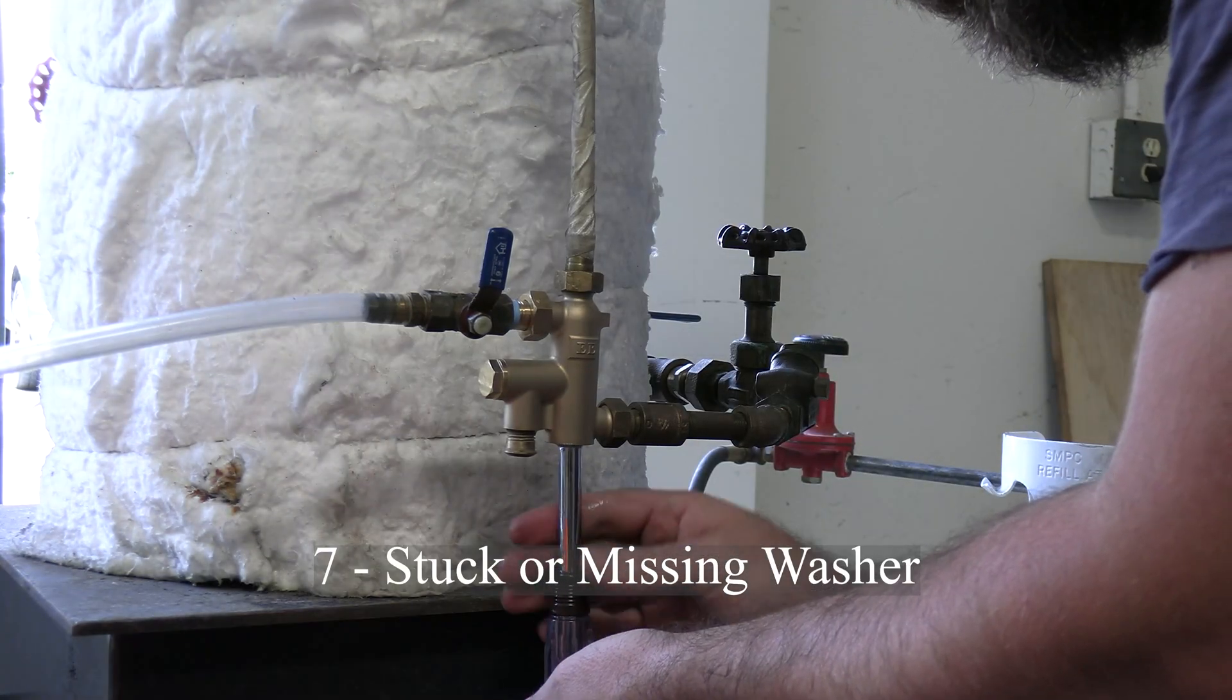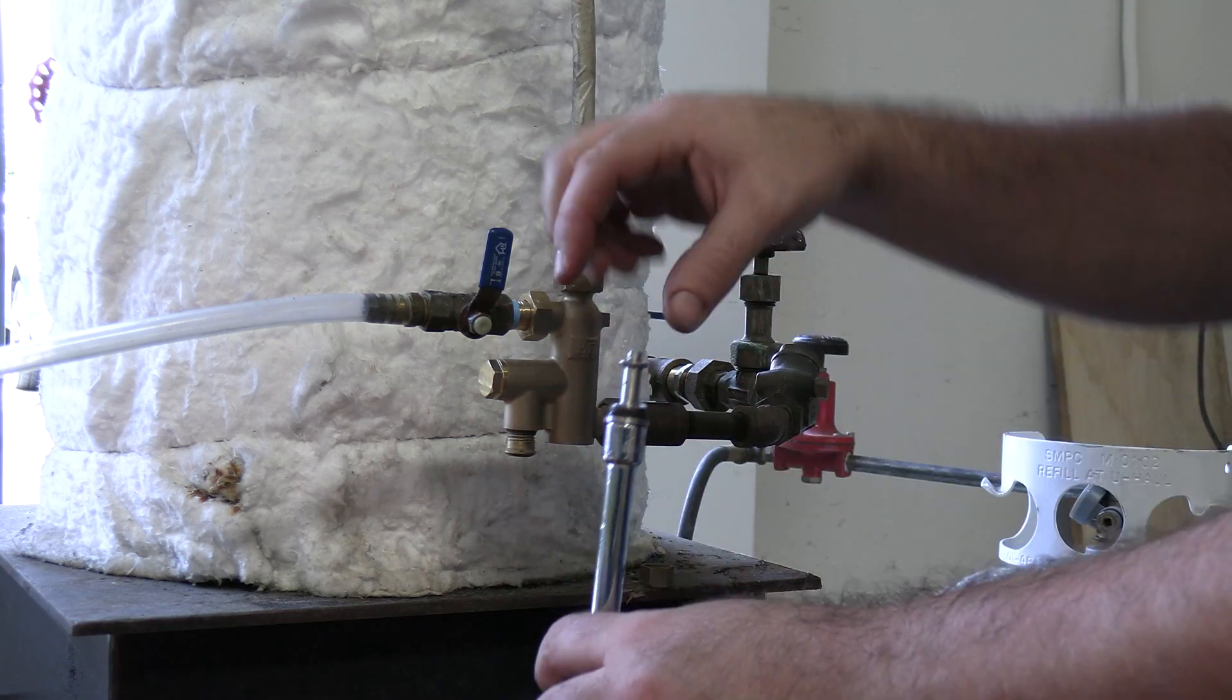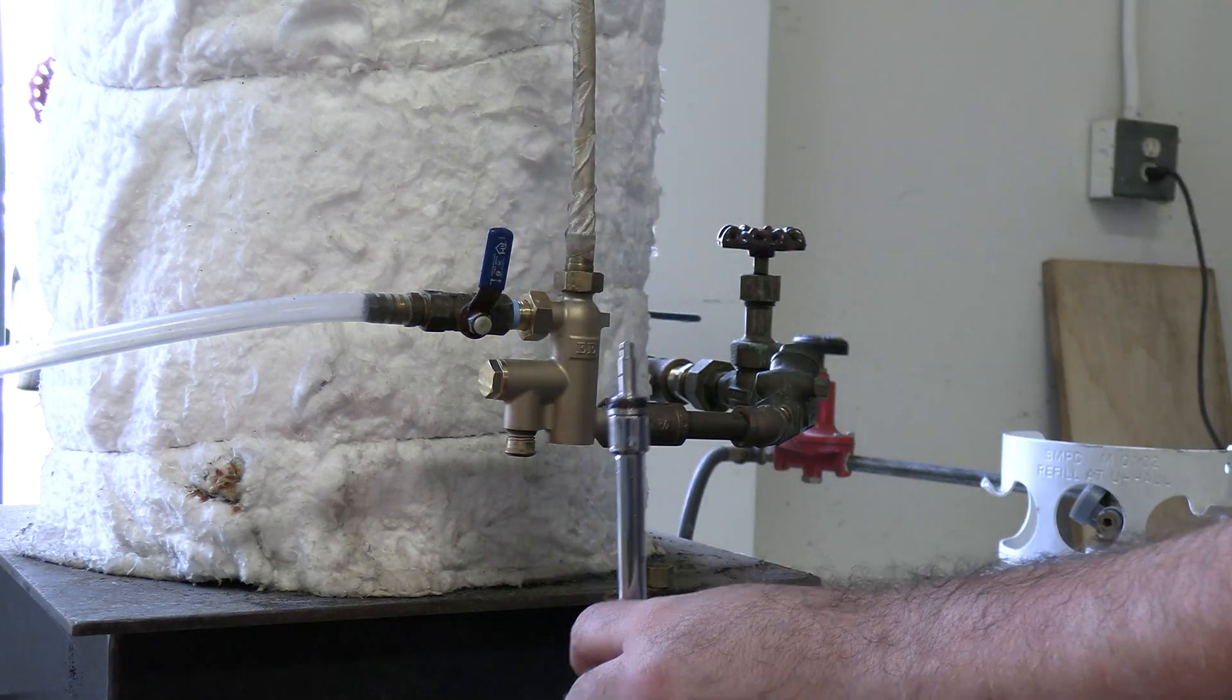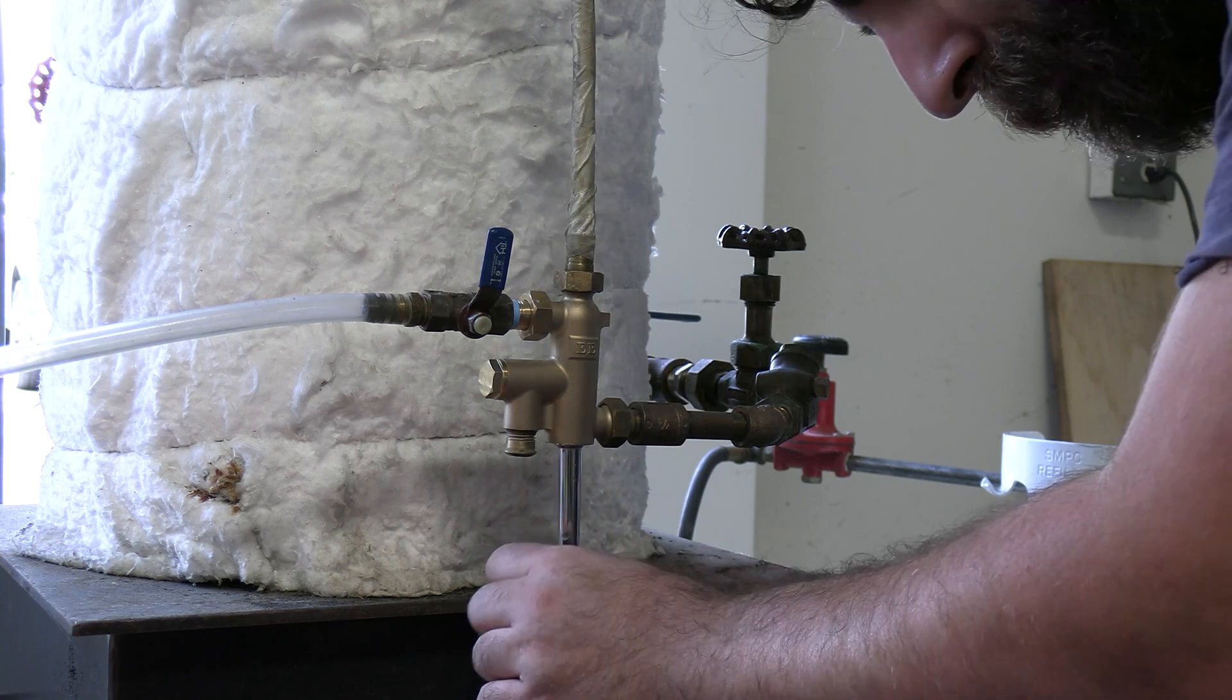A stuck washer has symptoms similar to an air leak. We can simulate this by simply removing the washer. So if you forget to put the washer back in after cleaning, this is also what you'll observe.